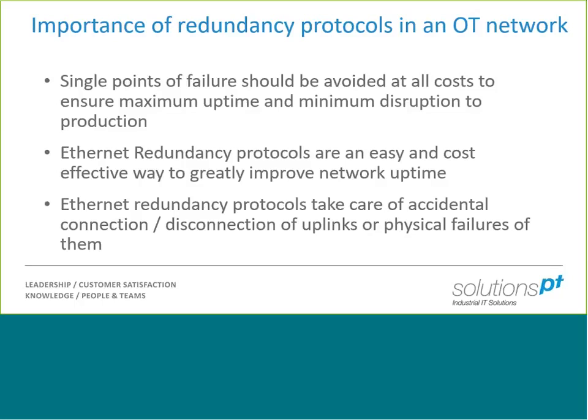Surprisingly quite a lot. If a network is running on a bunch of managed switches and we have a redundancy protocol in place, then things like these accidental connections are going to go completely unnoticed, because everything is going to run as normal. I have seen instances where unmanaged switches are being used and someone will accidentally connect, let's say, a bus network back on itself, so 3 switches connected back together, and without obviously understanding the implications of what they've done, they'll inadvertently bring the whole network down.